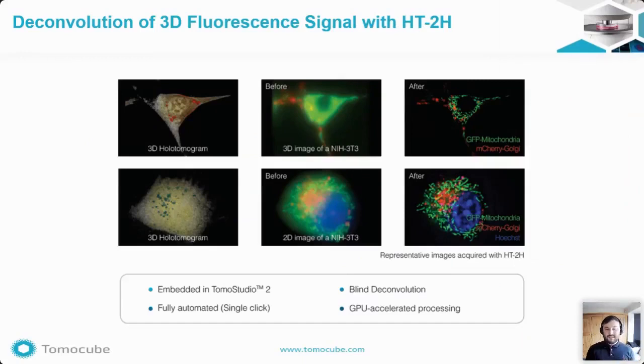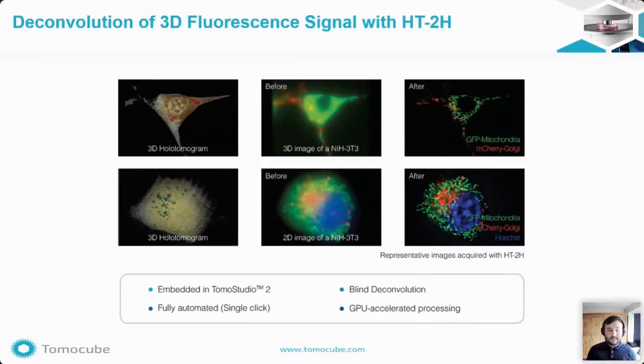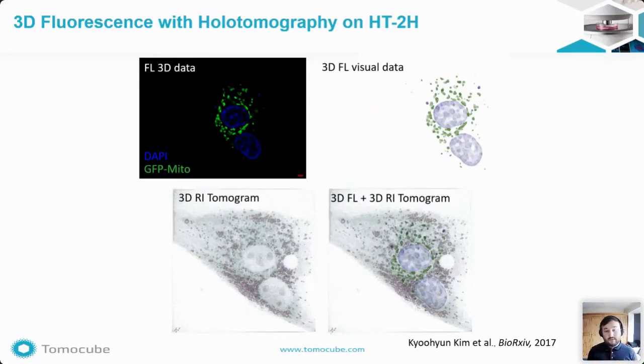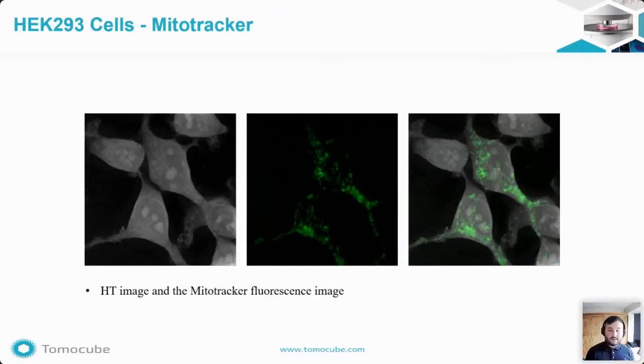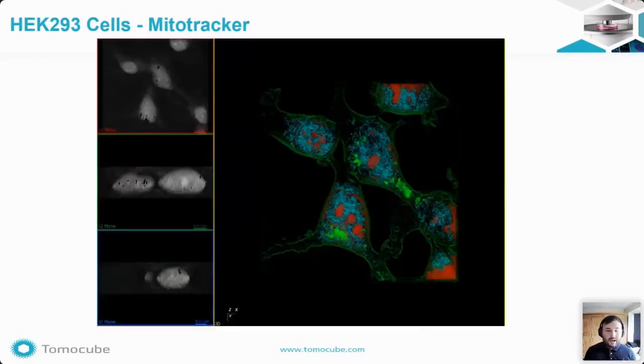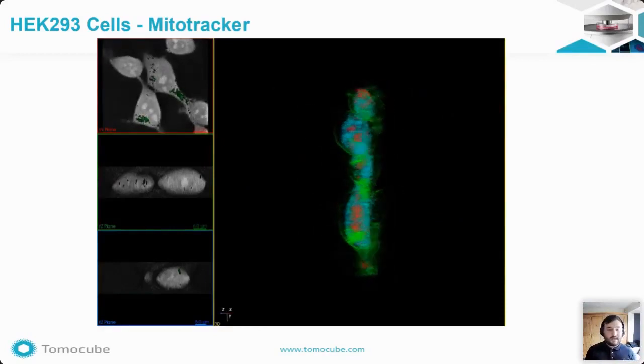It is important to remember that the specificity of labeling organelles with fluorophores is still important. Therefore, on the HT2H microscopes, we have incorporated correlative fluorescence capabilities. What sets the TomoCube microscope apart from competitors is that we generate both 3D QPI and 3D fluorescence data. This is made possible by taking fluorescence Z-slices and applying a deconvolution algorithm, allowing us to output true 3D phase and 3D fluorescence correlative images. In this example, the MitoTracker fluorescence signal overlays with the intracellular features of the holotomography images, and we are able to visualize it in 3D as seen in the video on the right.